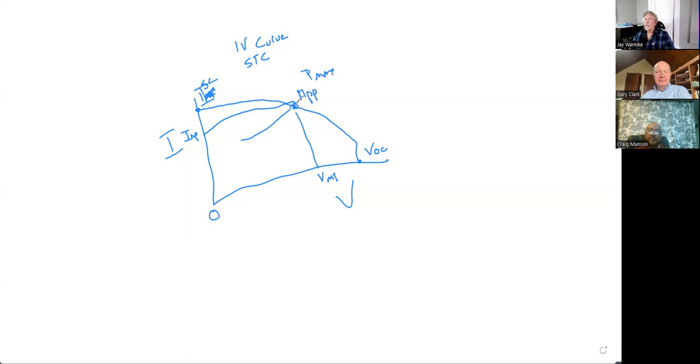All right, so this is where we're going to be operating at. Well, if I want to figure things like voltage drop, I want to know what's happening in the real world, I'm going to use the real world amperage and the real world voltage for that.